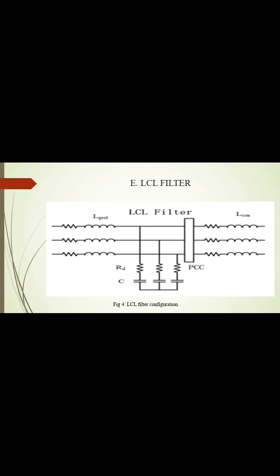This is the LCL filter. The passive filter is implemented to reduce harmonics, which cause disturbance in line current and voltage, resulting in poor power quality. Connected between the source and inverter, the filter carries out the function of filtering out current harmonics, which makes a balance between the source and inverter. An LCL filter is a third-order low-pass filter, which provides good harmonic attenuation and a small filter size.